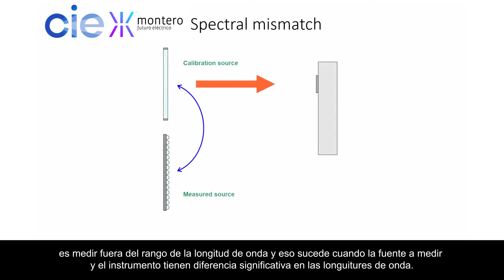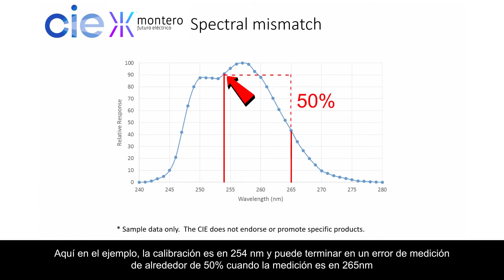Now, the responsivity of UV radiometers varies a lot from wavelength to wavelength, and this varies a lot from instrument to instrument. In the examples shown here, a radiometer calibrated using the 254 nanometer mercury line may end up with a measurement error of around 50% when measuring a 265 nanometer UV LED. This doesn't necessarily mean that the instrument is bad, it's about getting the calibration and the use of the equipment right. Other significant sources of error include neglecting correction factors.